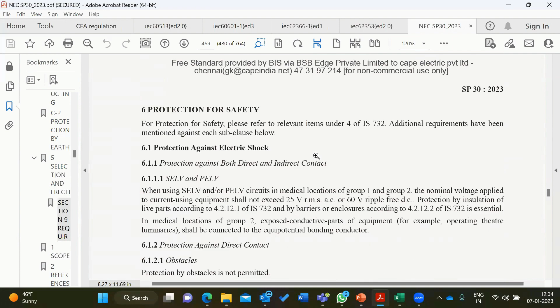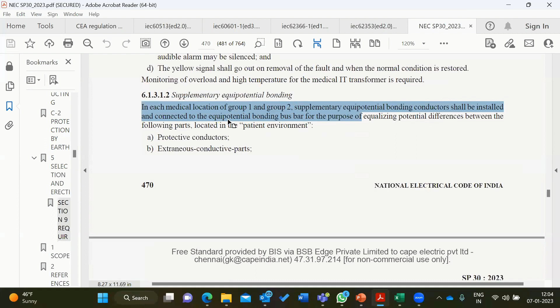It is called supplementary equipotential bonding. Supplementary equipotential bonding means in a medical environment, all the metallic objects in that area must be interconnected. In medical locations, Group 1 and Group 2, supplementary equipotential bonding conductors shall be installed and connected to the equipotential bonding bar. So what the standard says is you must interconnect everything together so that between two equipment, the resistance of the connection must be less than 100 milliohm. This is a technical requirement.